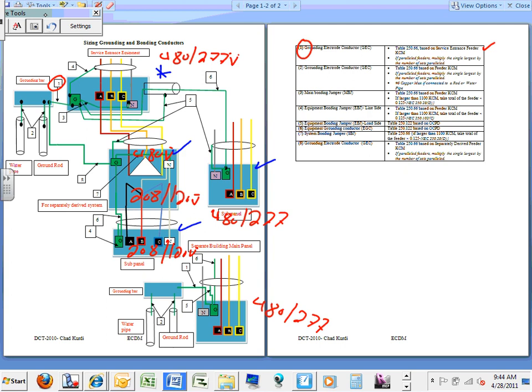Number two, guys, there's a special condition for number two. Number two right here is basically the grounding electrode conductor going to a pipe or a ground rod. The only reason I split this one is because you don't have to go more than number six. If you read number two, it says the same thing, 250.66, based on the service entrance conductors, and number six is the maximum. You don't need to go higher than number six.